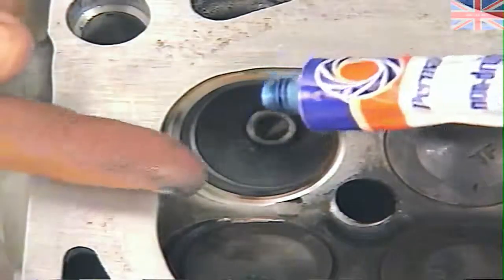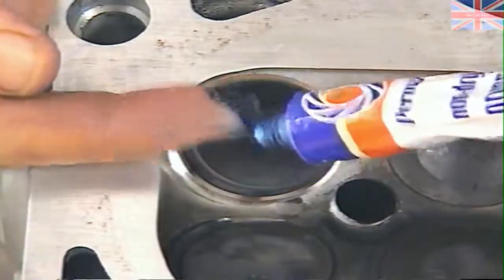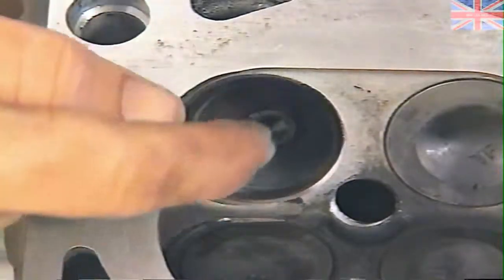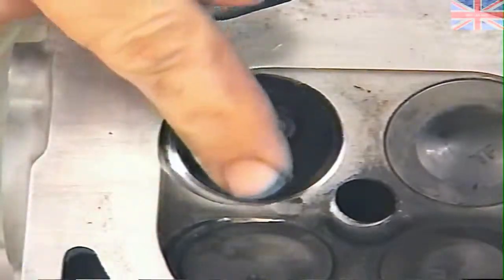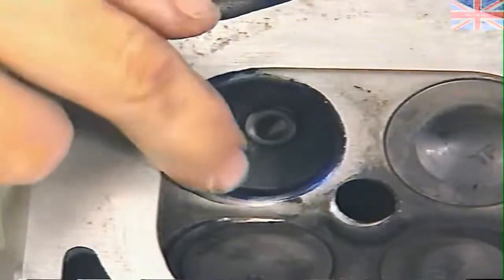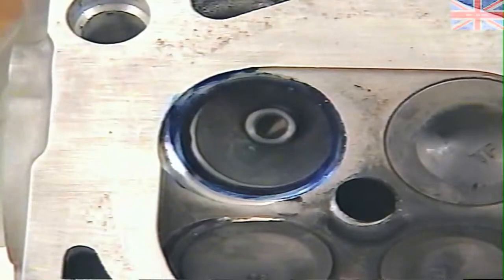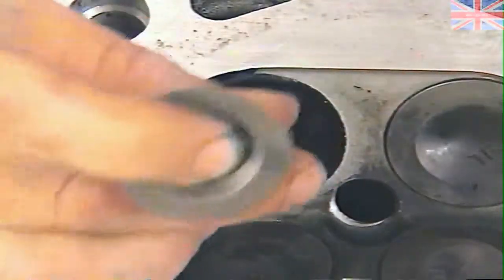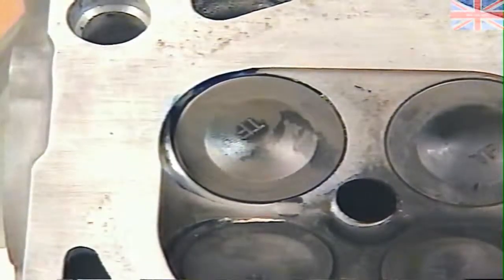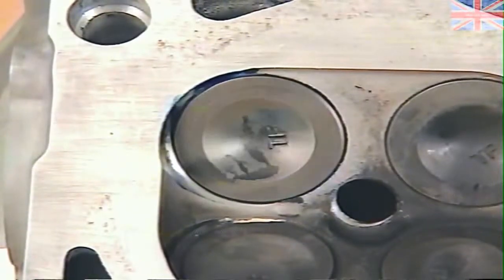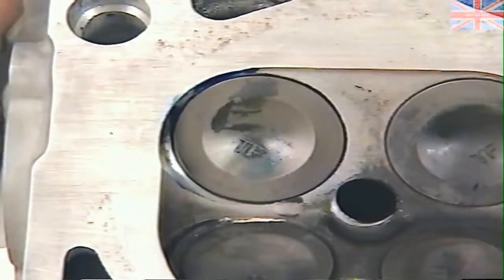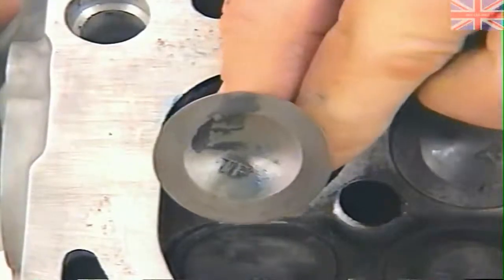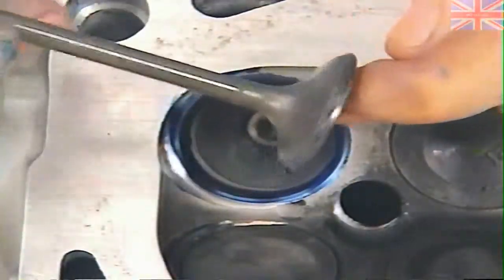Check the valve seat for even contact with the valve. To do this, put a light coating of Prussian blue on the valve seat. Set the valve in place and rotate the valve with light pressure. The blue should transfer to the entire width of the valve face for good contact with the valve seat.